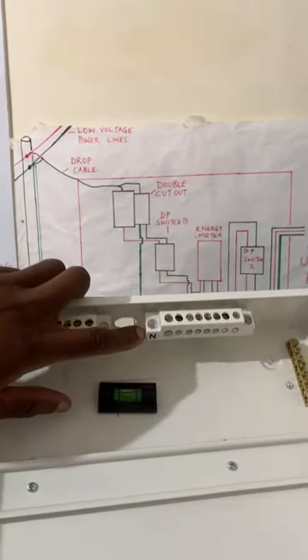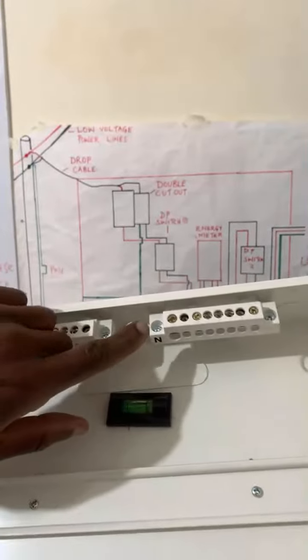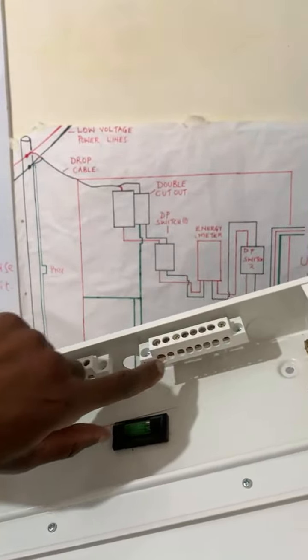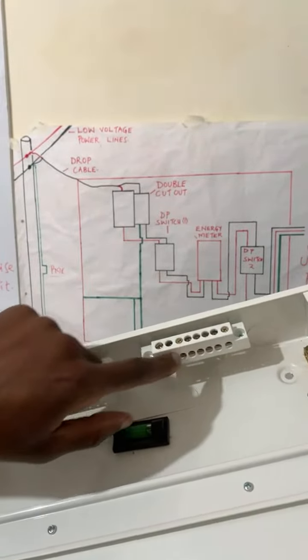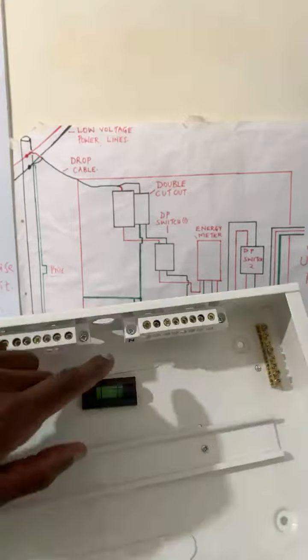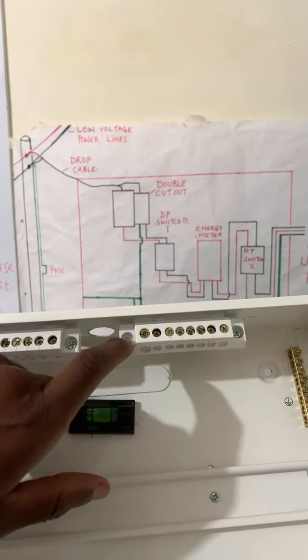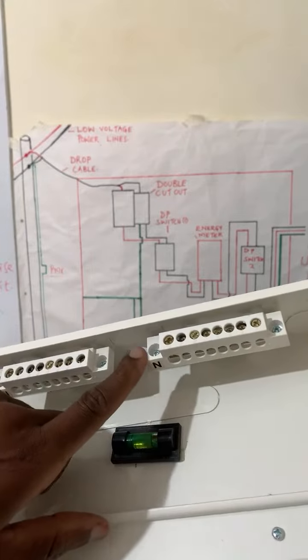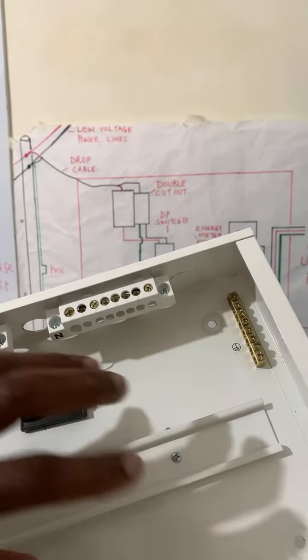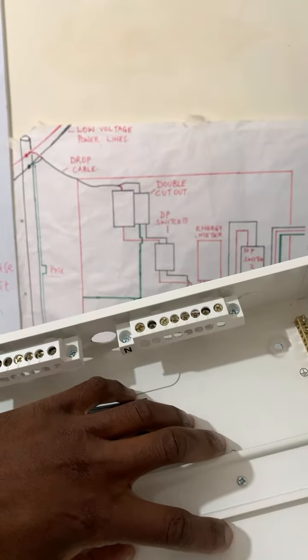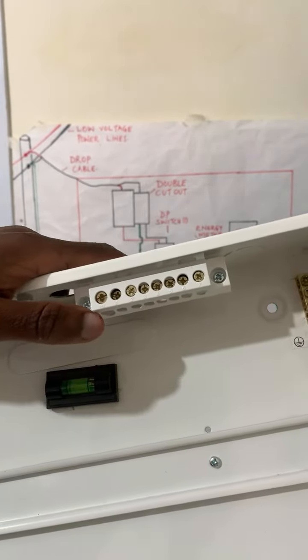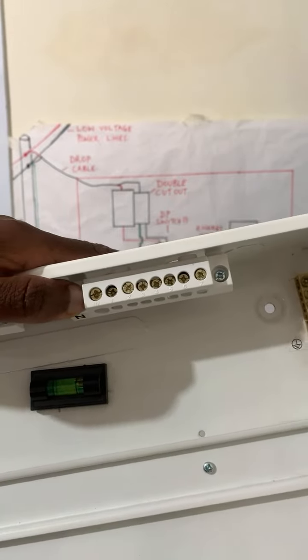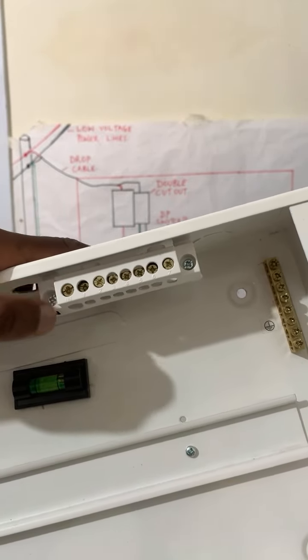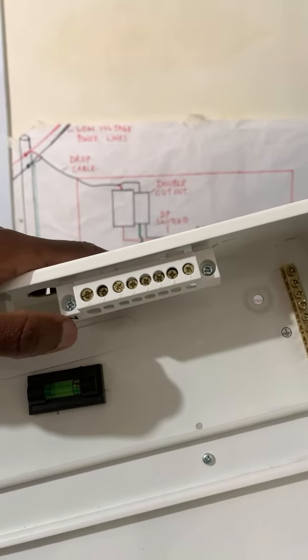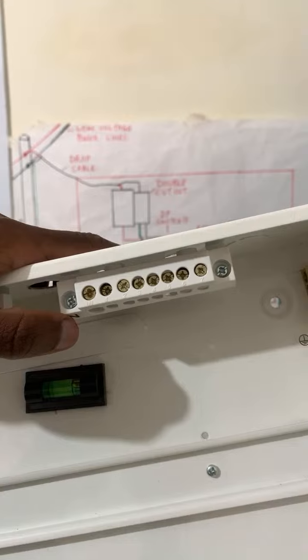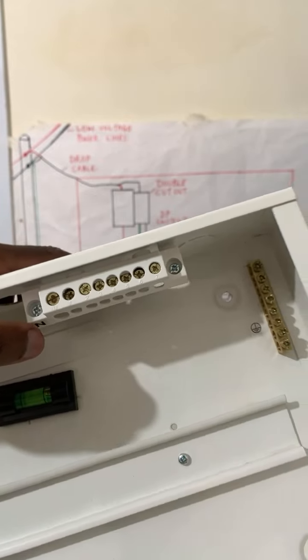But again, remember at this point where we have the neutral bar, the casing of this neutral bar is plastic. And the plastic has been screwed to the metallic part here so that it cannot be in touch with the metallic case. So that is how they cleverly avoided the issue of bonding earth and neutral at the consumer unit level. I don't know whether you have gotten that point, or should I repeat? Should I repeat my talk, boss?